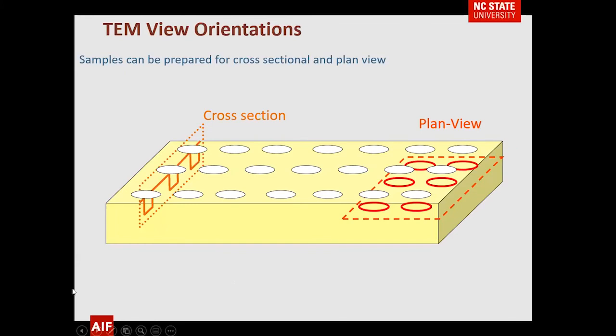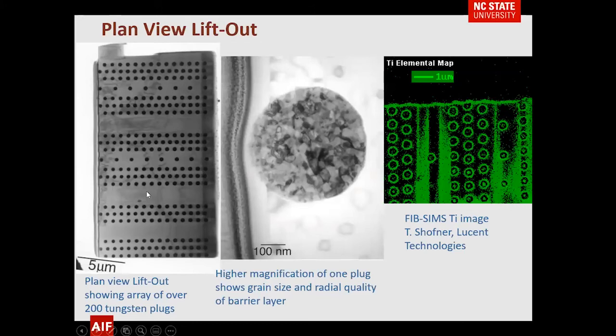So far we've talked about cross-section TEM orientations. It's also possible to do plan view — a little trickier because you have to think about how to mount the sample. If you take two pieces and glue them together edgewise, you can obtain a plan view section. Here's an example showing an array of over 200 tungsten plugs. In cross-section you'd only get one little slice out of each plug and couldn't assess uniformity of the cladding layer. We were also able to do FIB SIMS on the same sample, showing the titanium cladding uniformly around the plug with no discontinuities.